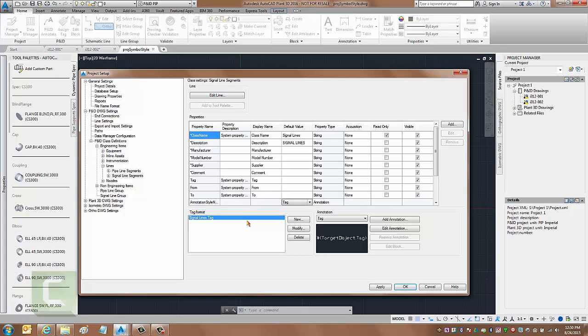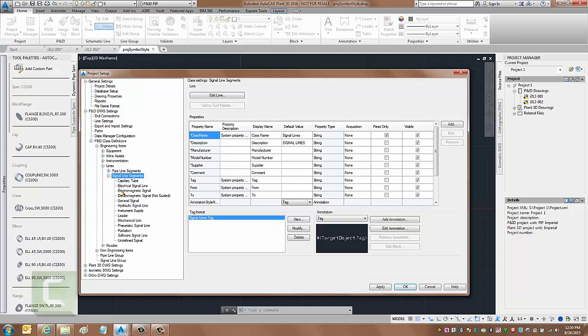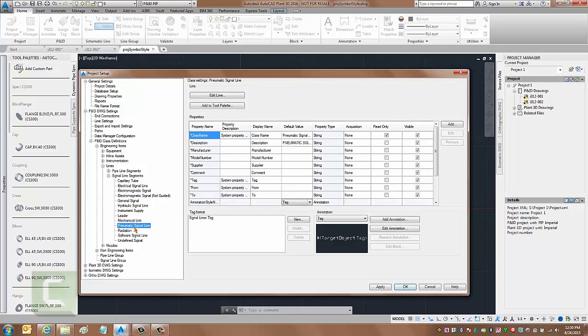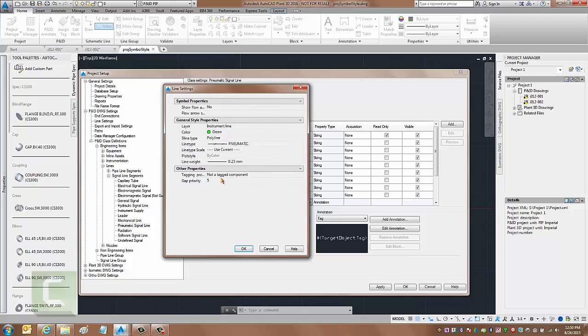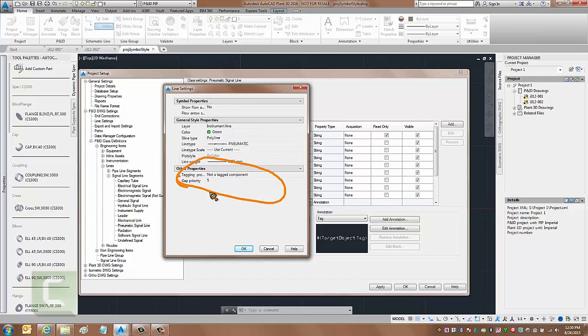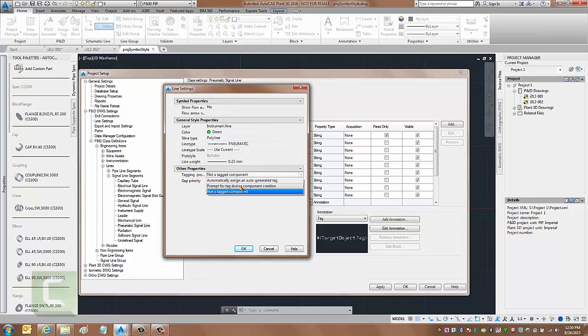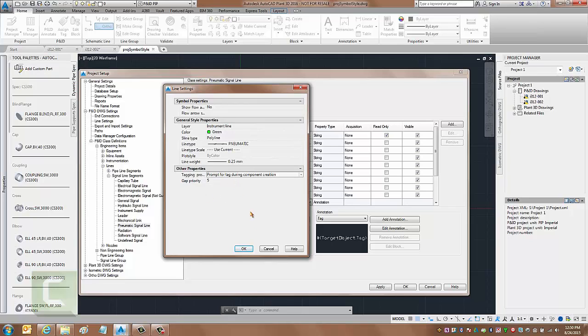So that set it up to where I have a tag format. Now I have to be able to tag those lines. Because even at this point, if I went to try to tag one of those lines, assign tag is going to be grayed out, because I have to go to each individual line. Since my drawing was using a pneumatic signal line, that's the one I'll go to first here. And do an edit line. So selecting the pneumatic signal line, edit line here. And I'm going to set the tagging prompt right here. Where it says not a tag component, I'm going to change that to prompt for a tag. If I do not do this, there's not any method I can use to tag that line.